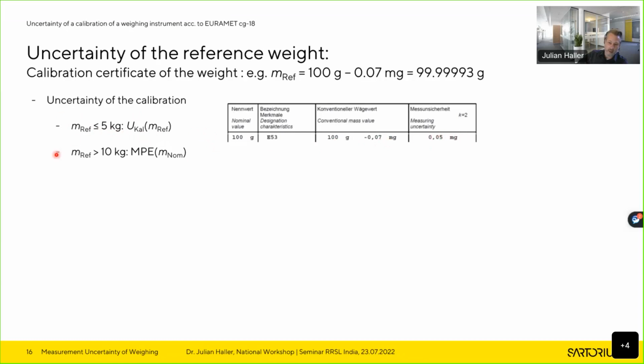But for higher weights, for which you only have weighing instruments with a coarser scale interval, it is usually sufficient to consider the nominal value and the MPE of the weight. So that makes it easier, but it is only usually sufficient for, let's say, 10 kilograms and above.